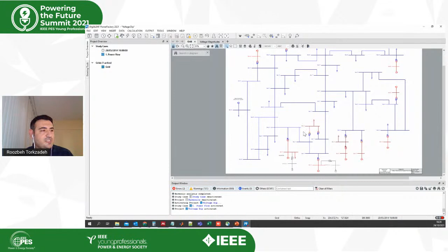For doing that, you need to right click on the bus and then go to calculate and then select short circuit. Here in the window, you can see that you can calculate the short circuit based on different methods. I'm going to use this IEC 60909, and also you can select the version of the standard that you want to use. In 2016, they also considered the contribution from the renewables, so I will select this one. It will be a three-phase fault with maximum short circuit current.